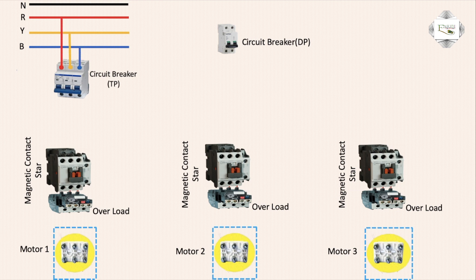For the first motor: the TP input takes red, yellow, and blue phases. The TP outgoing connects to the magnetic contactor input, and the magnetic contactor output goes to the motor terminals U1, V1, W1.